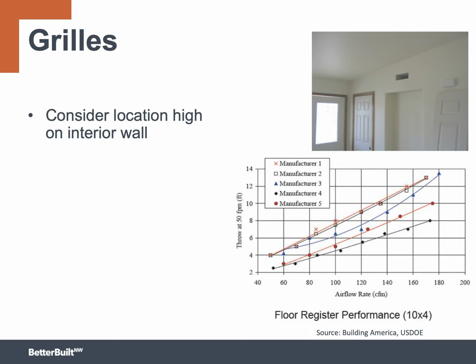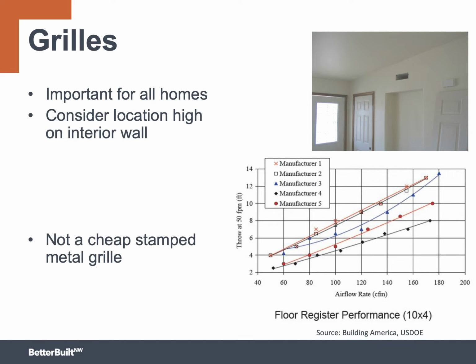But there is one step that will ensure that this all works out. The key is going to be selecting the appropriate grill. The chart shows the difference in airflow from different types of terminal grills. The line on the bottom is the standard stamped metal grill that you probably find in most houses today. You can see there's quite a bit of difference. That simple stamped metal floor grill is probably not the best choice for good mixing in a room.